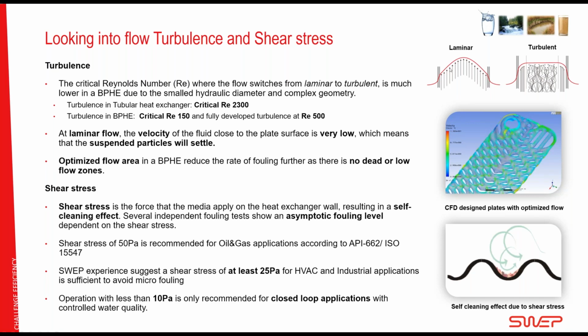Why is this important? Well, at laminar flow, you will have a velocity gradient, so the flow will be very slow in the corners or close to the wall of the heat exchanger, and this will allow the suspended solids to settle, and it will also drive up the wall temperature, which will be important for scaling. So laminar flow is bad for microfouling, and it's bad for scaling. And turbulent flow is good against microfouling because it keeps the suspended solids running around, and it will also make the wall temperature lower because the heat transfer is much more efficient. So that's why turbulence is so important.